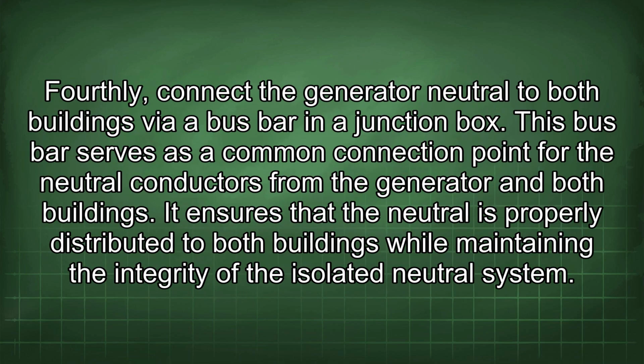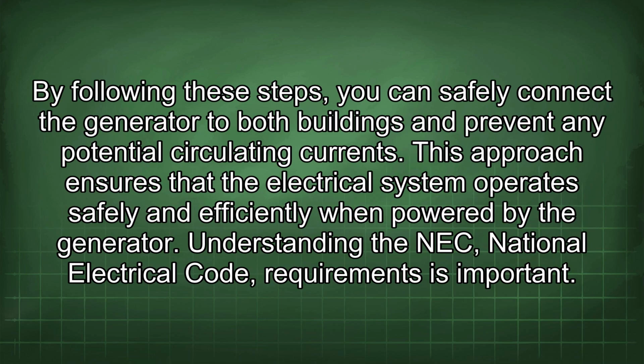Fourthly, connect the generator neutral to both buildings via a bus bar in a junction box. This bus bar serves as a common connection point for the neutral conductors from the generator and both buildings. It ensures that the neutral is properly distributed to both buildings while maintaining the integrity of the isolated neutral system. By following these steps, you can safely connect the generator to both buildings and prevent any potential circulating currents. This approach ensures that the electrical system operates safely and efficiently when powered by the generator.